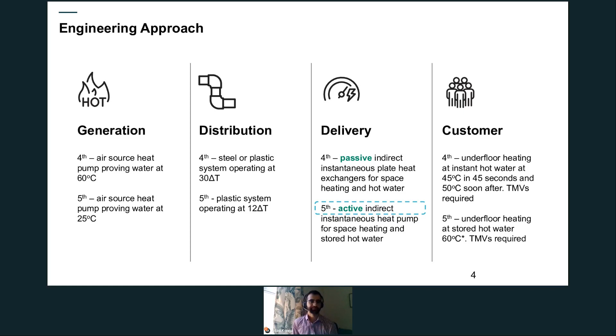So comparing the two systems, assuming that you've got an average flat, it's got 3,500 kilowatt hours a year, we're just assessing really the energy performance. So purely the energy balance in these two systems. So using an hourly model of the predicted performance, the 4th gen air source heat pump system is slightly worse from a COP perspective. Obviously it has to lift water temperature from 30 to 60 all year round. The 5th gen system is slightly better as it only has to do the 6 to 25 degree lift.